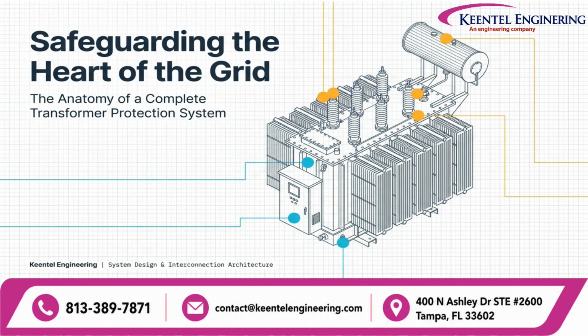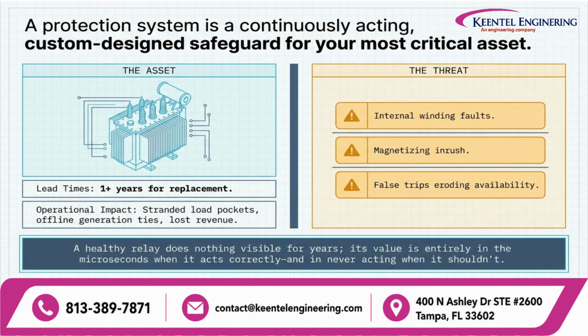In this presentation, we'll look at the anatomy of that protection system, from the sensors and protection elements to the trip circuit, commissioning process, compliance requirements, and real-world engineering challenges. The objective is simple: detect genuine internal faults quickly, avoid unnecessary trips, and ensure that when a trip command is issued, the transformer is actually disconnected from the electrical system. A protection system is a continuously acting, custom-designed safeguard for one of the most critical assets in the power system.